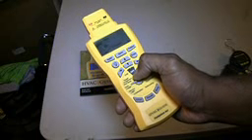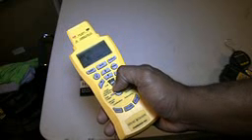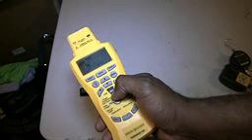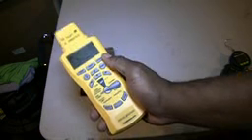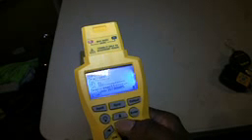I can also go out to the condenser and check my pressures. I can also check with the AC clamp accessory head, check the motor amperage off of both the indoor blower motor and the outdoor compressor wirelessly. I can sync all that information on here, and it allows me to set a time span. Let me see if I can bring that in so you can see it. At the very top where it says span, you can choose how long you want to run the test, and it gives you the option of seconds, minutes, hours.